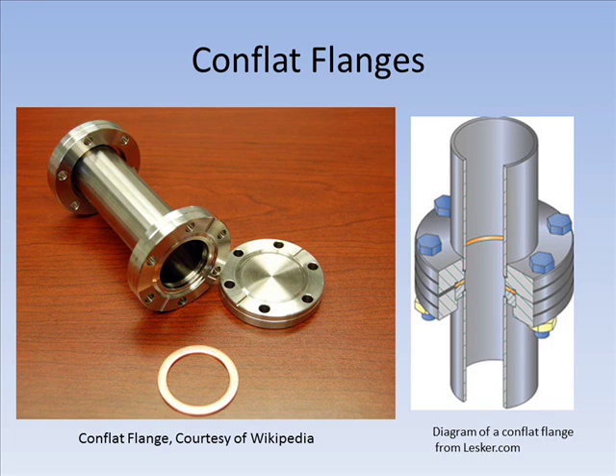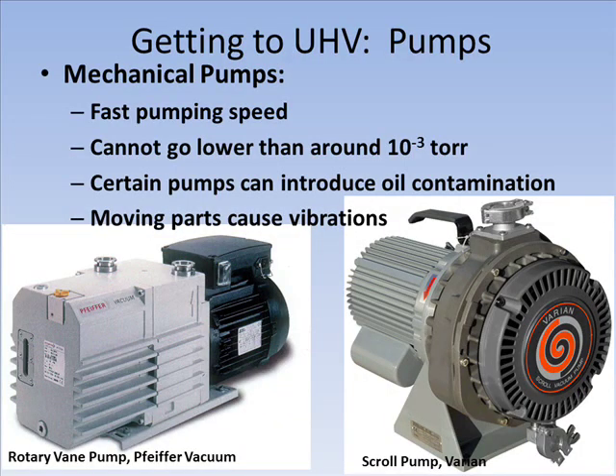This type of flange is called conflat. Other flanges exist that create the seal by using different types of gaskets and different mechanisms to tighten the flanges together, but the general principle is usually the same. The chamber and flanges can be sealed as airtight as you like, but they're pointless without a way to evacuate the gas from inside the chamber. To do this, various vacuum pumps must be used. Traditional mechanical pumps have a high throughput, but they cannot attain UHV on their own and they have a host of other problems. For this reason, these pumps are used to pump vacuum chambers down from atmospheric pressure, but other pumps are needed from there.